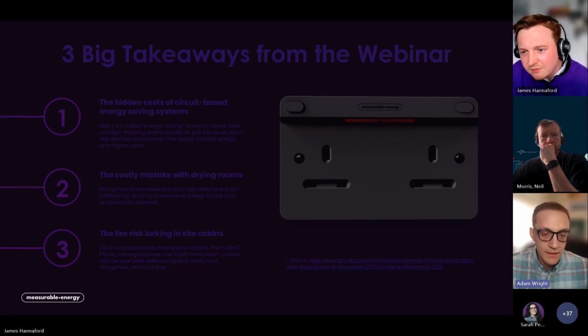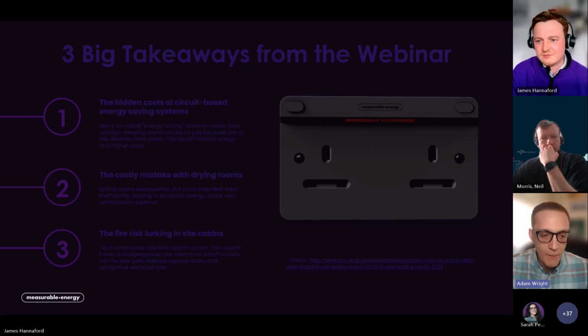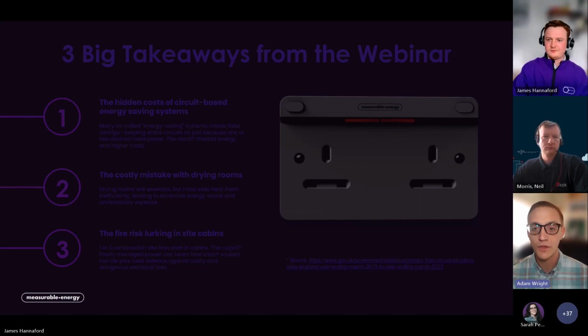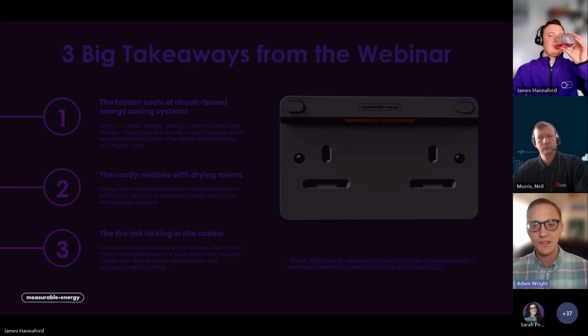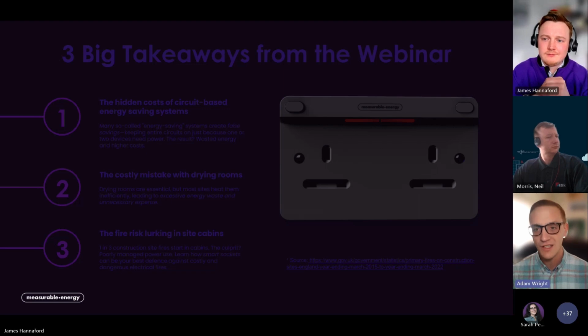Yeah, so yes, Jamie, this is exactly what is happening on a lot of sites. We have an overspec generator. It's a very, very small battery. Battery's getting used up very, very quickly, and then there is damage to the generator. There's damage as well as high energy costs. And this is sort of the whole point here. If overnight load is reduced enough so that it fits within that battery, then we reduce the need for that generator to kick in. It's difficult because every site's slightly different. So there's almost a need to spec generators out to begin with and maybe reevaluate as the site's up and running to optimize that. But yeah, you've hit the nail on the head that damage is literally happening, and we're saying that this is a way to start preventing it.